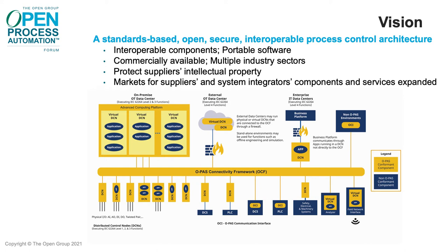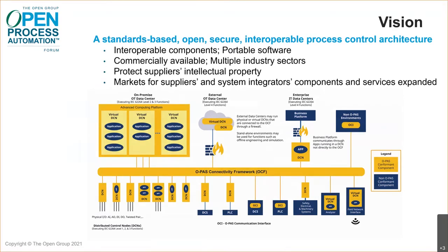OPAS systems are centered around a connectivity framework based on OPC UA, which facilitates communication between any participating control nodes, which we usually call DCNs, or distributed control nodes. DCNs can be dedicated to I/O for measurement and control, or to computation, a mix of both, a gateway to systems such as PLCs or DCSs, or to other equipment such as analyzers or non-OPAS subsystems.